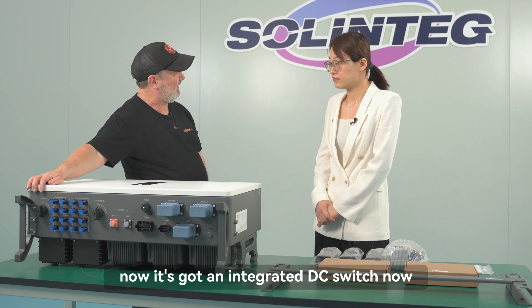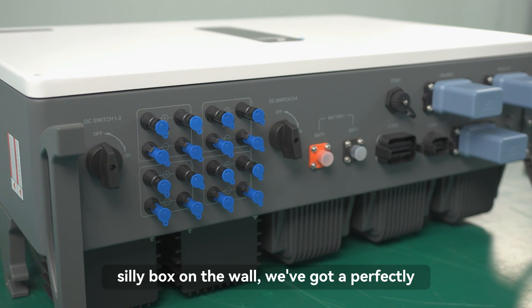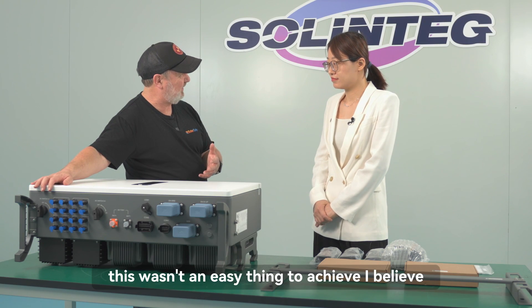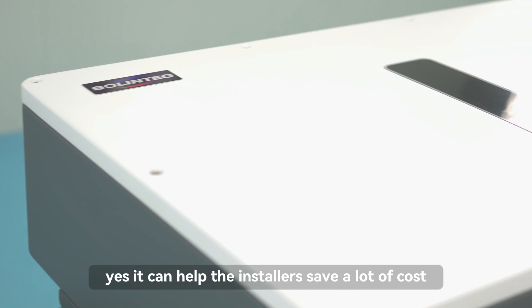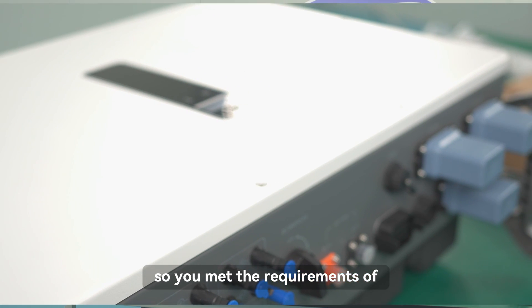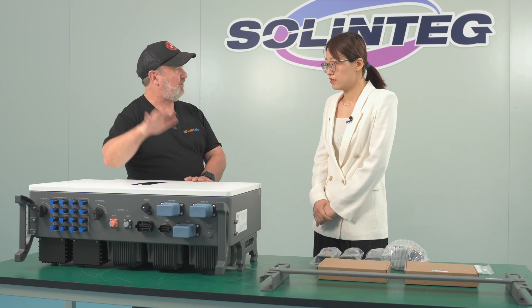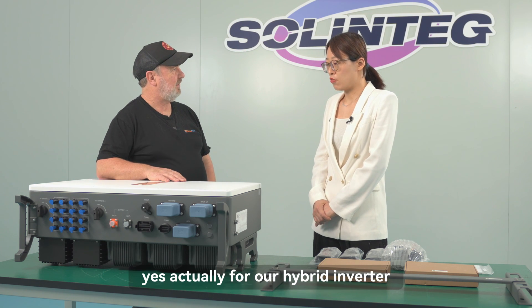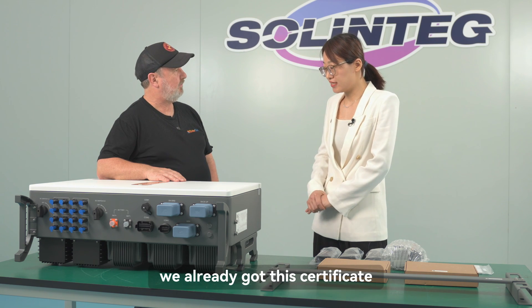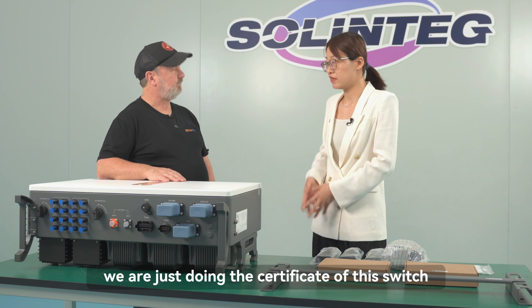It has an integrated DC switch, which is a big deal for Australia — it means we don't need another box on the wall. This wasn't easy to achieve, but it can help the installer save a lot of cost and time during installation. For our single-phase inverters from three to eight kilowatts, we already have the IEC 60947-3 certificate. For the three-phase hybrid inverter from 25 to 50 kilowatts, we are currently obtaining the DC switch certificate.